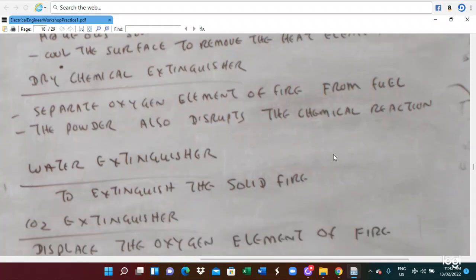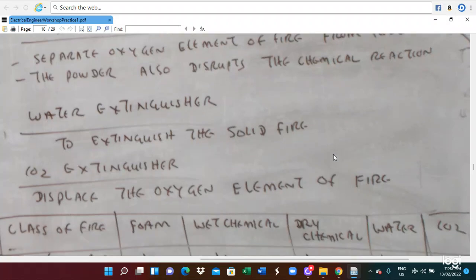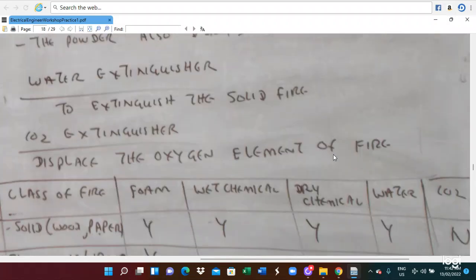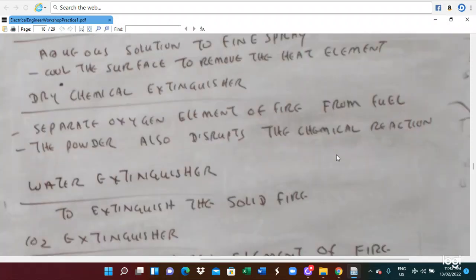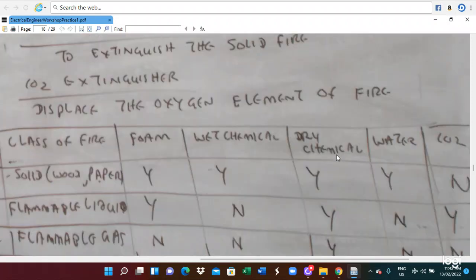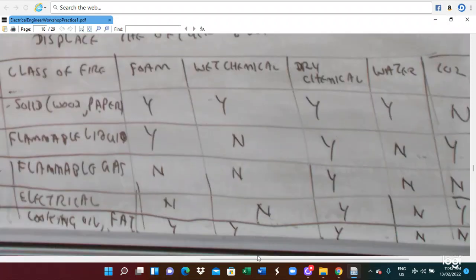Water extinguishers are used to extinguish solid fire. So this is the carbon dioxide fire extinguisher. They displace the oxygen element of the fire. So this is the kind of fire extinguisher and the type of fire you have to use. So this table shows the class of the fire. If your fire is solid, wood or paper, you can use foam, wet chemical, dry chemical, water, but you cannot use carbon dioxide. Flammable liquid, you can use foam, you can use wet chemical, you can use dry chemical, you cannot use water, you can use carbon dioxide.